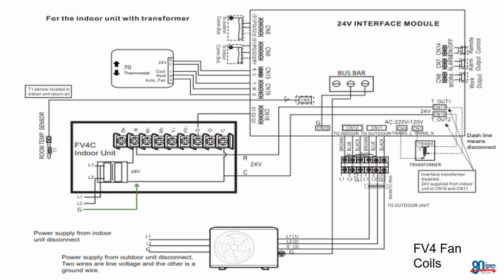Of course, we're going to have our power, our L1, L2, and signal feeding directly from the outdoor unit into the 24-volt interface. Now, it's important to note on here that you'll see where it says to outdoor unit. You need to make sure that you wire those wires appropriately and not to the one that says to indoor unit, because if you do, you're going to get a communication interference between this interface itself and the outdoor unit. So we want to make sure that we wire that up to the appropriate terminals.